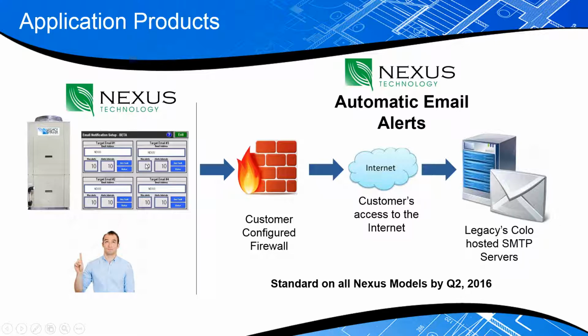Our data will be streamed from the PLC directly to our colo here. It's a secure colo, and you can program in where you want email alerts to go, how often you want them to go, or just whether you want an update on how the chiller is operating. So if you have sites that are remote and you want to know immediately if there's an issue with the chiller, you have the ability to do that. This has become a very popular feature.